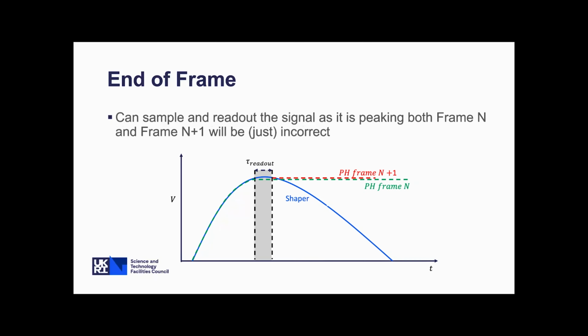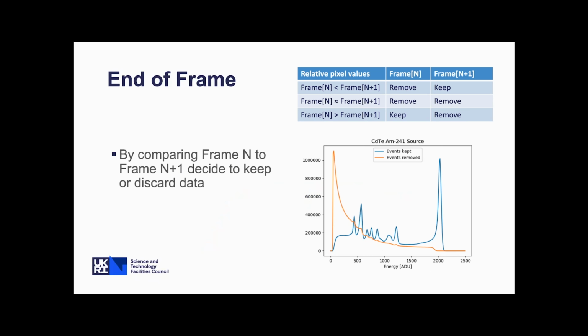Or we can happen to read out the peak hold signal just as the signal is peaking. This is very difficult to identify, and most likely in these scenarios we've got the false reading in both frames. So we've got these different scenarios, and then we can keep or remove the data based on that. By following these rules, we can remove a continuum of data caused by false events, by not reading out the fully formed signal, and we can recover true events, which is the spectrum in blue, the americium spectrum which we're expecting to see. So that's another correction that we apply to the data to make sure we get the best performance.